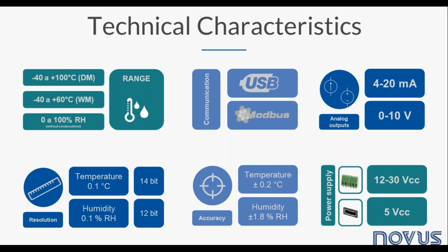Temperature has 14 bit and humidity has 12 bit. The accuracy is better than 0.2 degrees Celsius for temperature. For relative humidity, the accuracy is 1.8%. The two analog outputs can be configured as 4 to 20 milliampere or 0 to 10 volts, independently, just by software. The Climate can be powered from 12 to 30 VDC in the internal connector or from the USB port during configuration or commissioning.